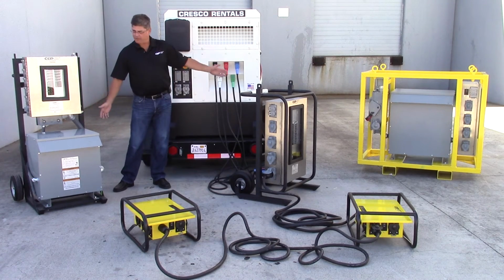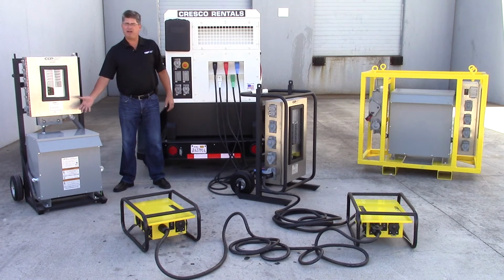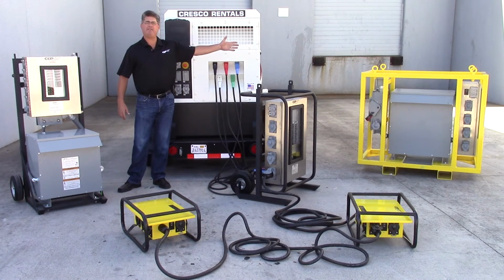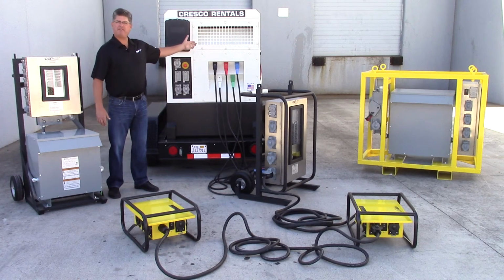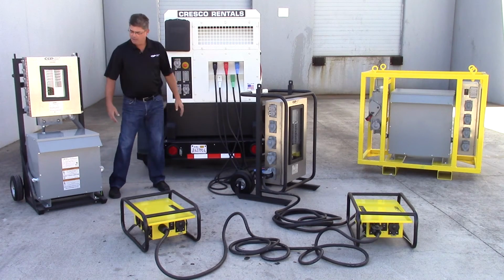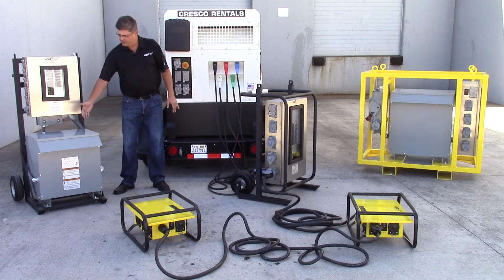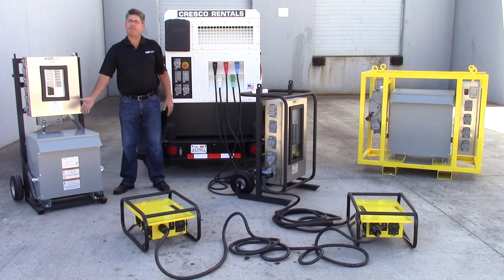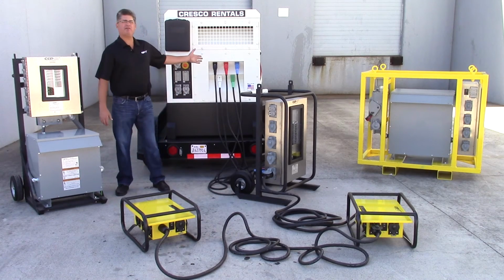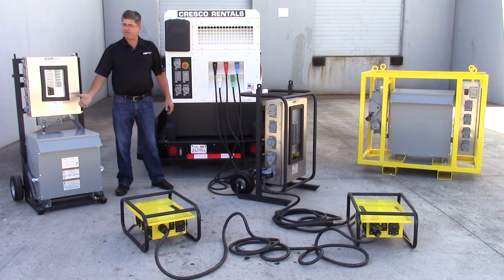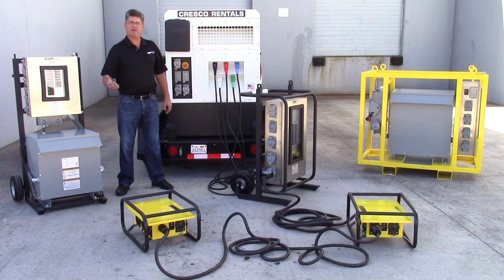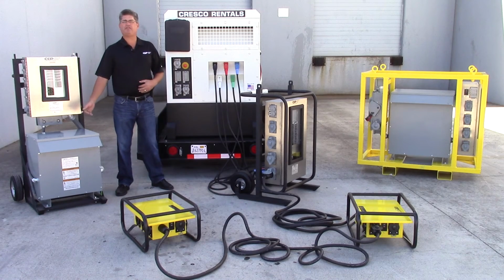I have 2 different units here. This happens to be a 30 kVA for smaller applications, and over here we have a 75 kVA, which would be the perfect mate for this 70 kW generator. Over here, basically what we're doing is taking the 480 volt power and stepping it down into your usable 120/208 power, similar to what the generator is actually putting out. However, the reason we're running 480 volt, as you remember, is because we want to have the most efficient power we can to the power source, and therefore we're using a much smaller diameter cable to run that 480 volt power over to these units.